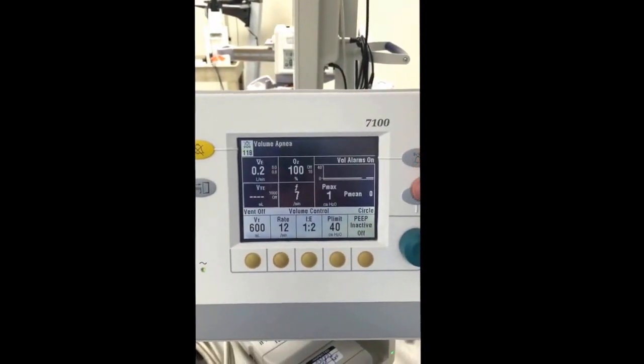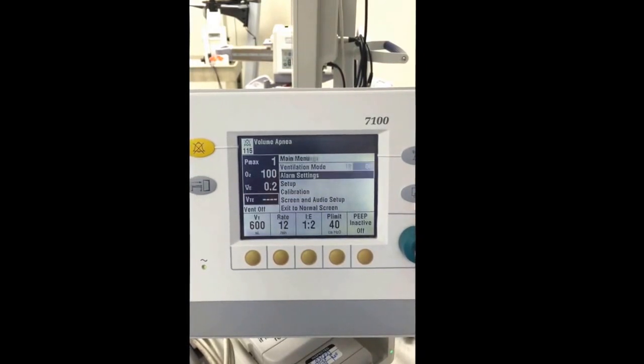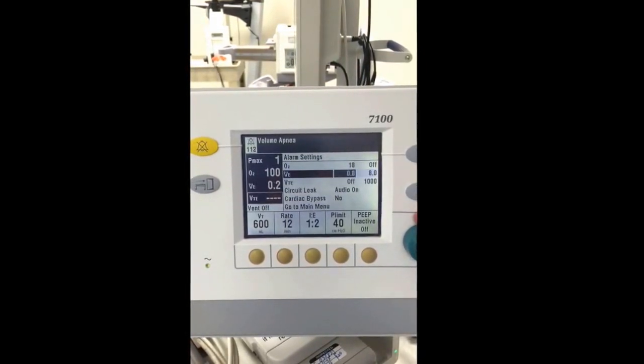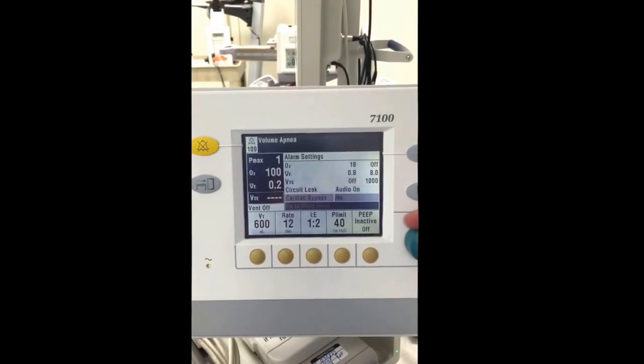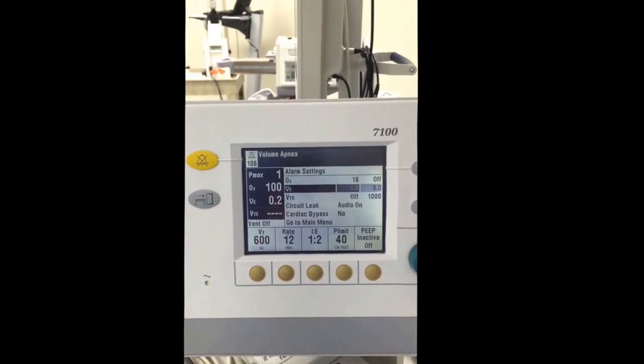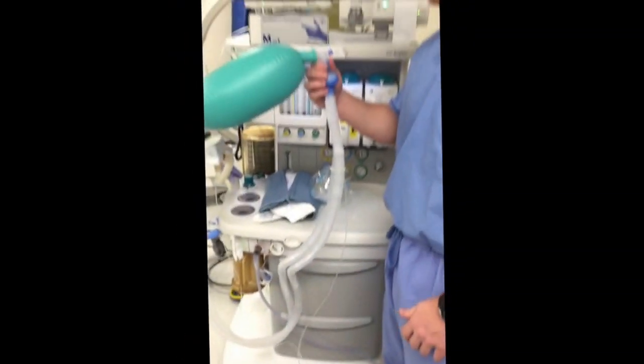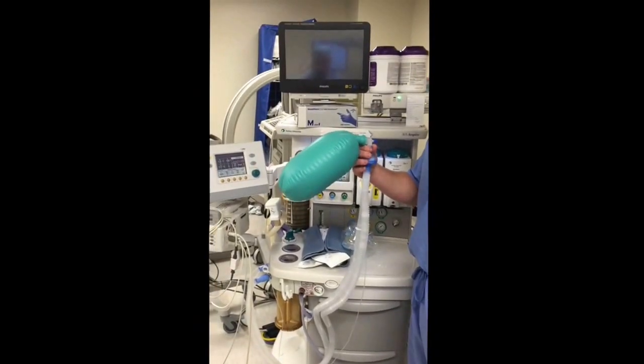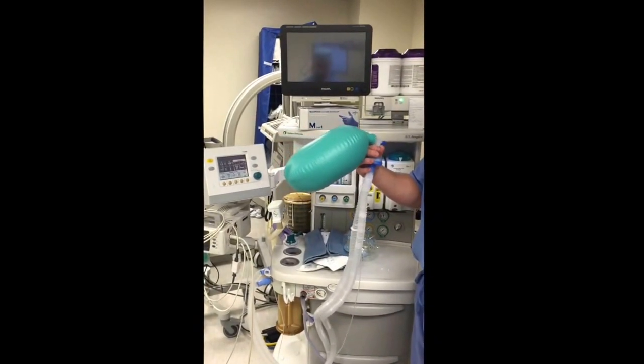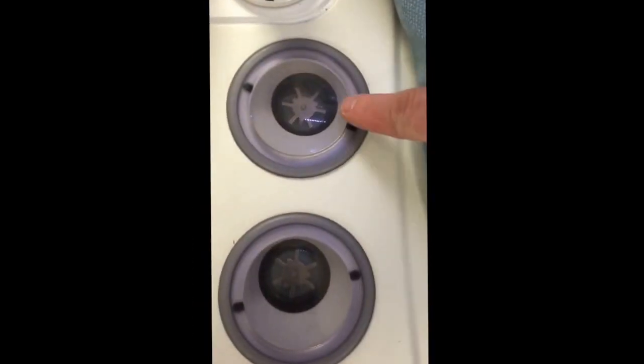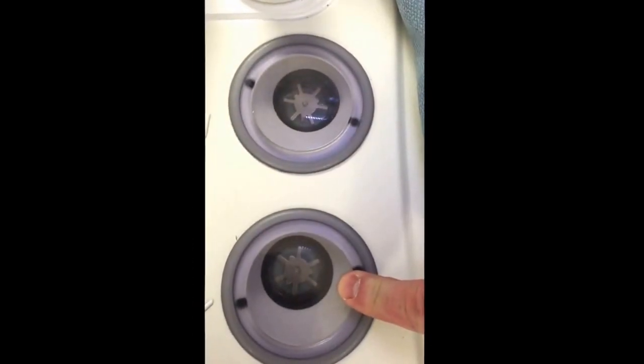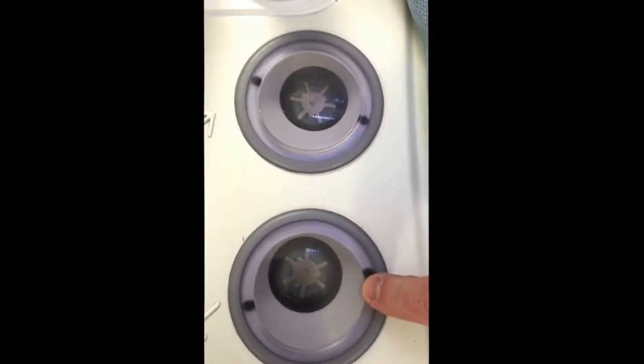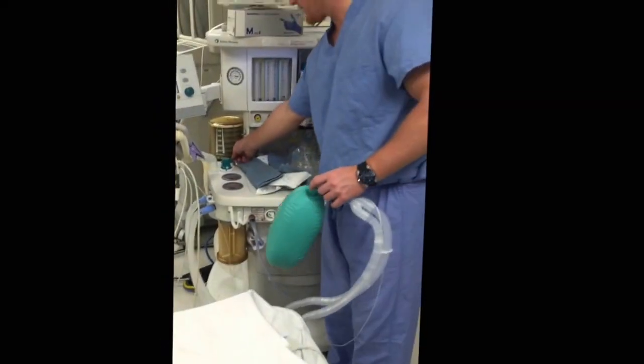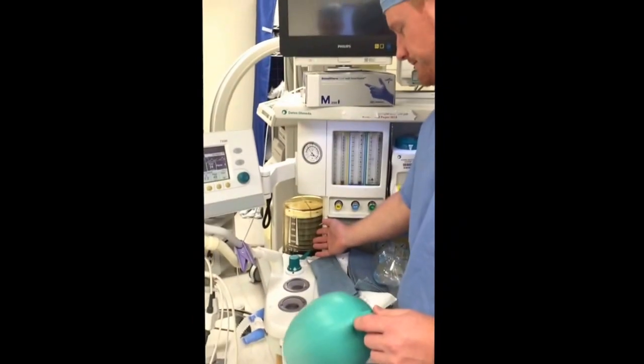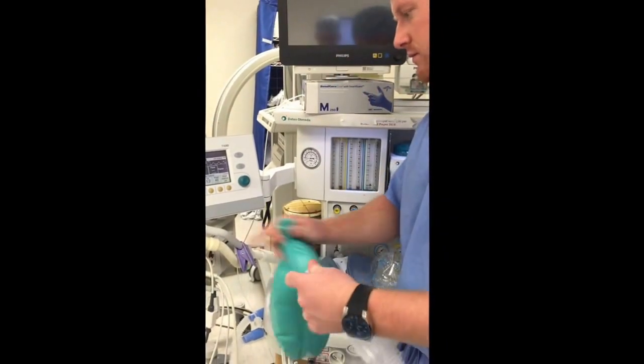So adjust your alarms by going to alarm settings, and as we all learned, the most important is the minute ventilation alarm, and make sure that all alarms are on and functioning. As you can see, there's no leak. Our artificial lung here is functioning correctly, and the inspiratory valve and expiratory valve in the ventilator are one way and functioning. Like I said, I like to wait and leave my bellows up. Switch back to my bag mode.